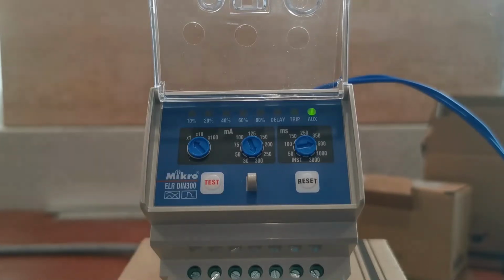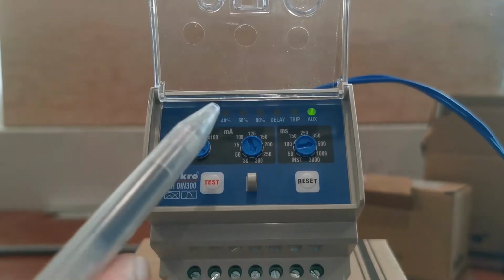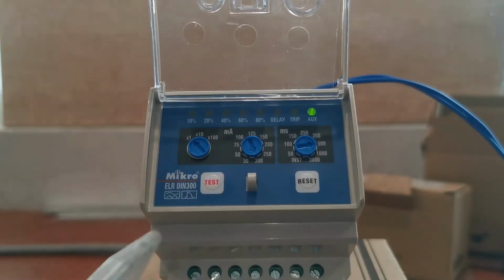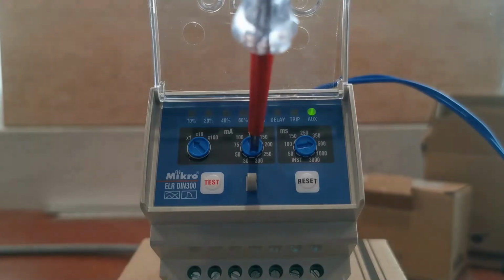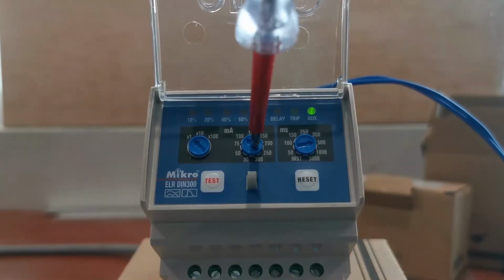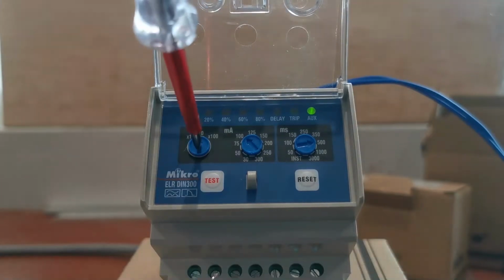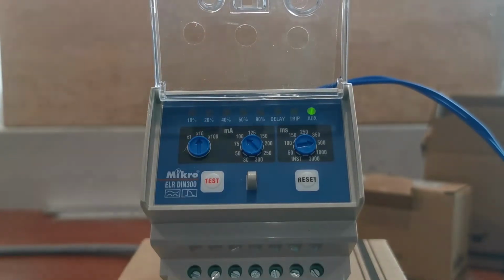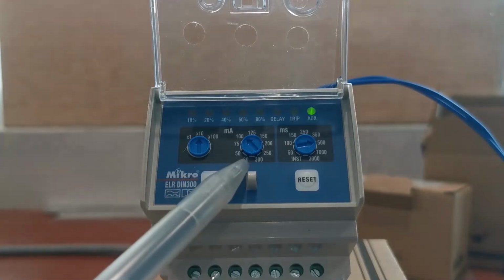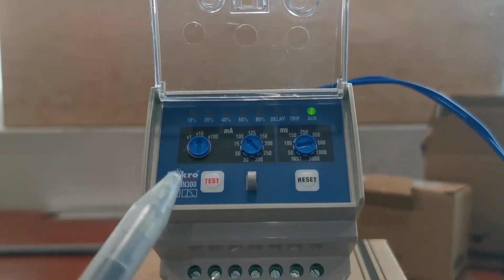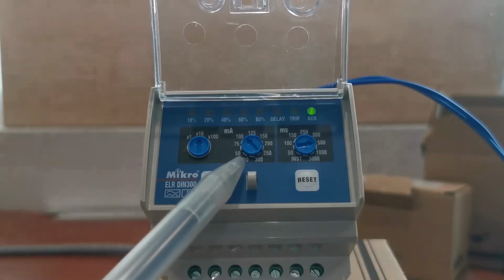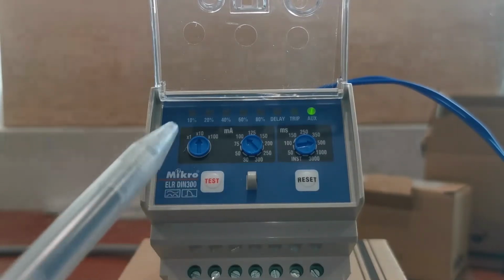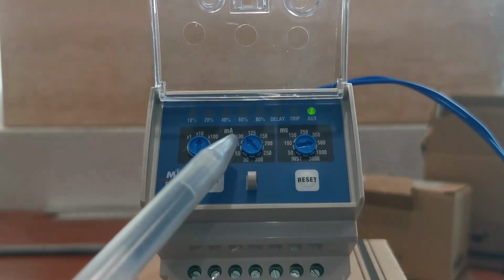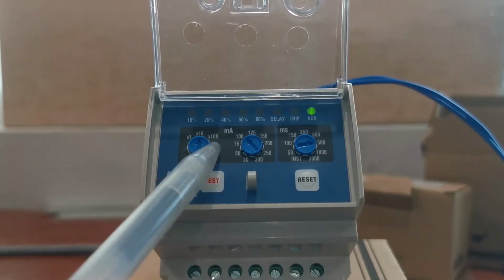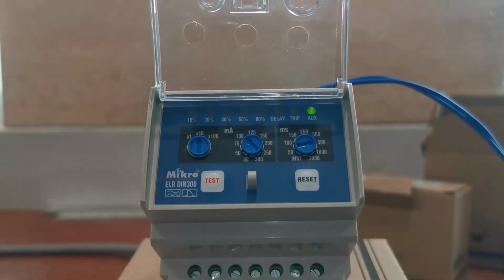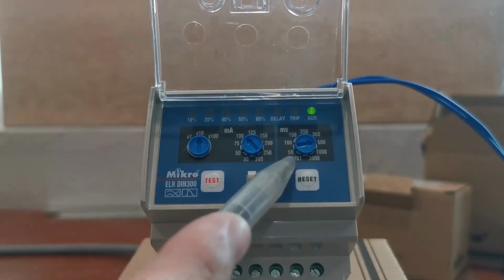For example, if I want to set 1 amp, I can change my dial to 100 and times 10. The setting range for this ELR is from 30 milliamps to 30 amps. So you set 30 milliamps by setting 30 here, multiply by 1. To set 30 amps, you turn the dial to 300 and multiply by 100. The time setting range for this ELR is from instantaneous to 3 seconds.